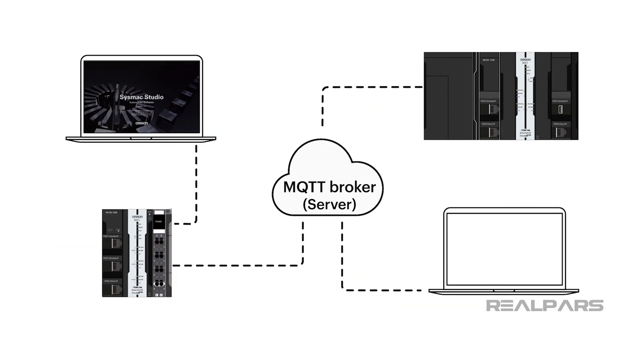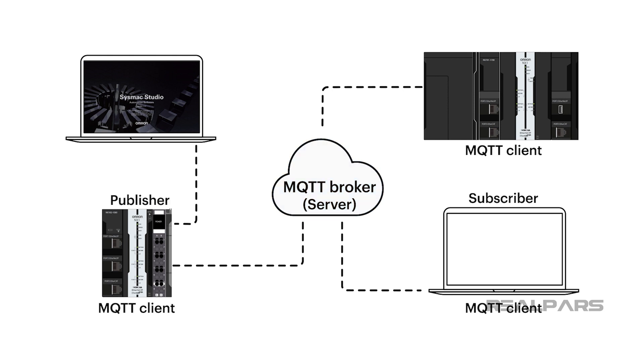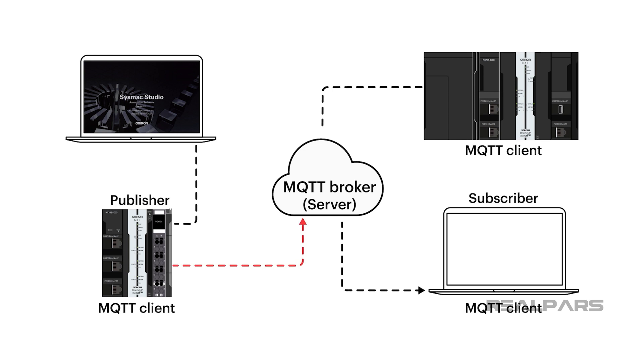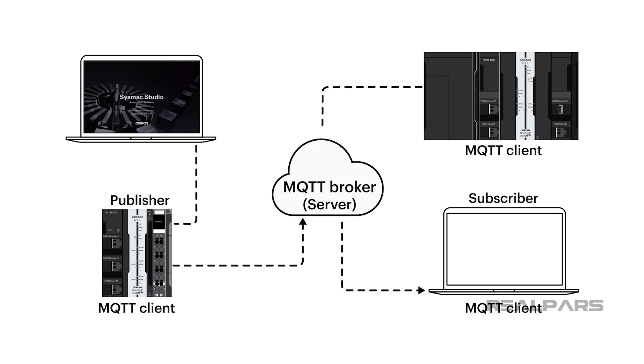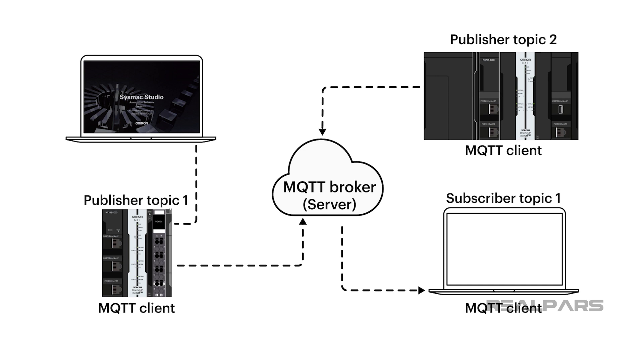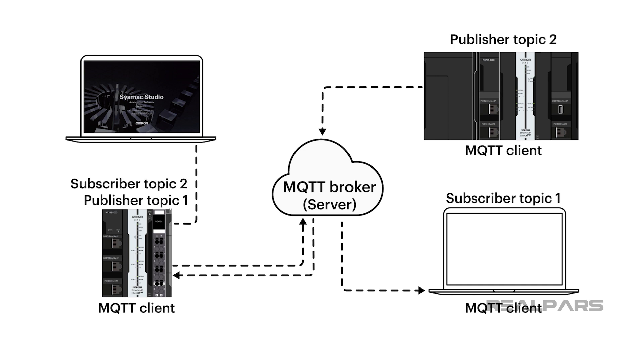MQTT uses an MQTT server or broker intermediary entity that enables MQTT clients to communicate. The server collects published messages from MQTT clients and delivers the messages addressed to receivers that were subscribed. An MQTT client can work simultaneously as a publisher or a subscriber on several topics. In our example, the NX controller is an MQTT client.